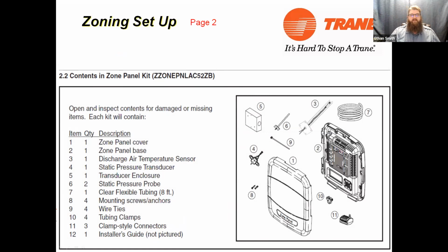Your zoning panel comes with a discharge air temperature sensor, which is required. You also have a static pressure sensor and a couple pitot tubes. They give you some tubing. They give you these little weird jobbies that we'll talk about in a minute, and they give you housing for that static pressure sensor and a bunch of screws that are pretty useless. You use your own screws. I don't know anyone that's screwing Phillips head screws into ductwork anymore.